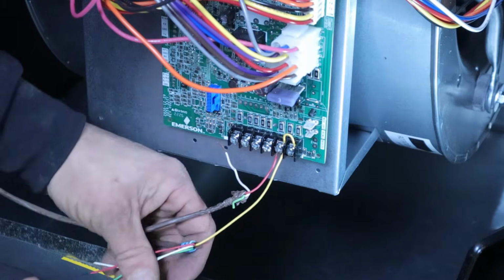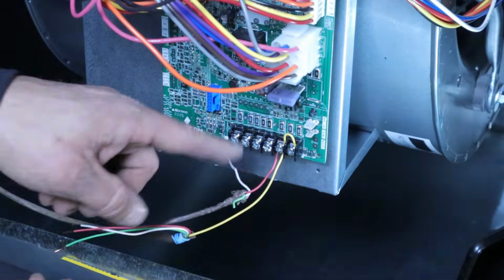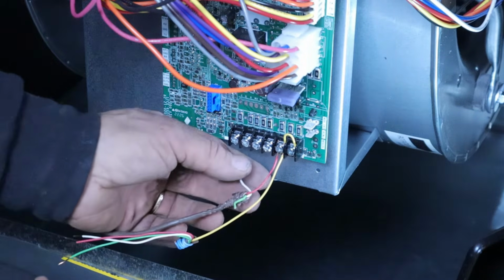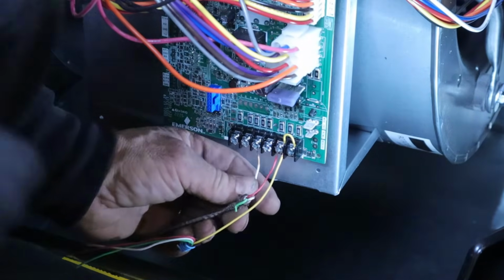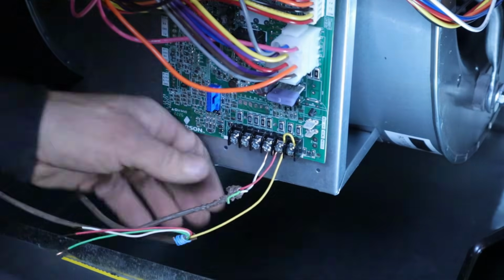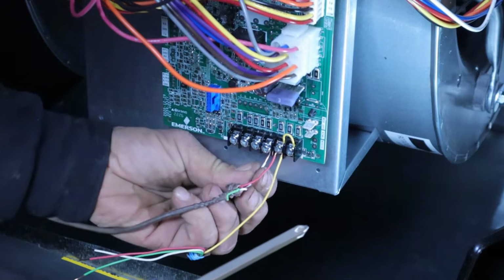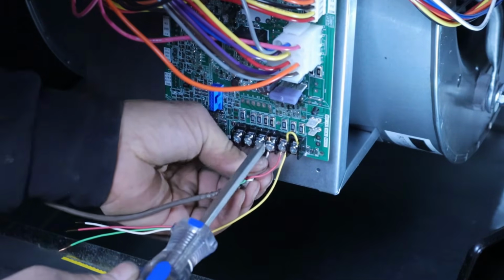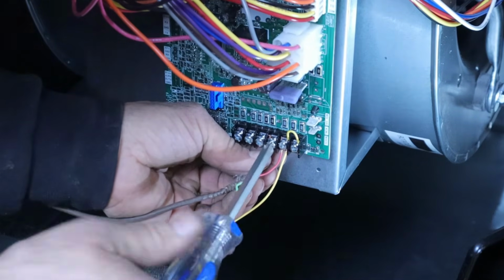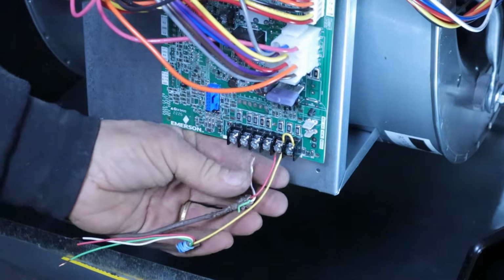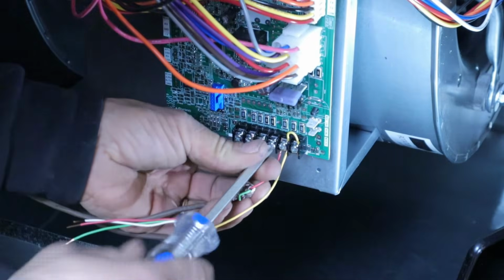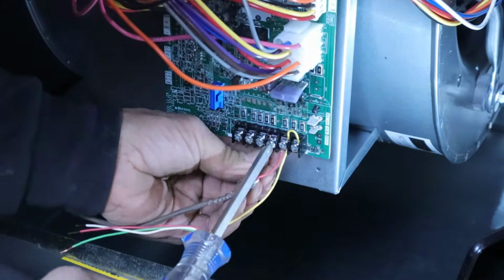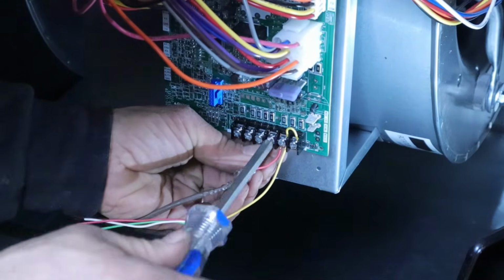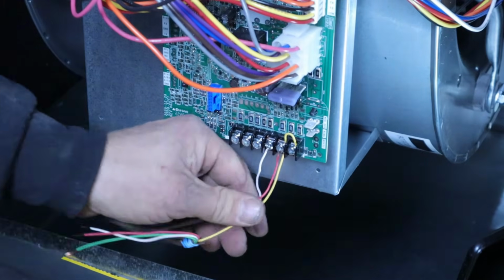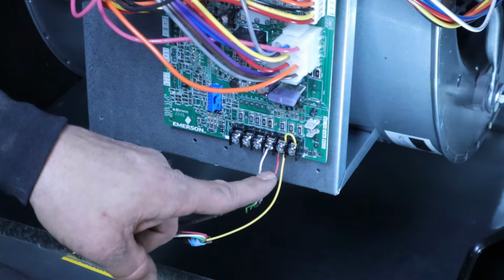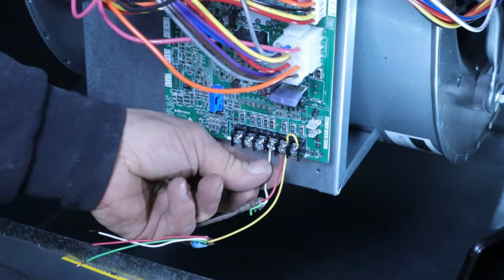So the white wire coming back from the condensing unit, that's our common. When the 24 volts goes out to the condensing unit to close the contactor, it's going to come back on this white wire, and we're going to hook that up to common. Our common connection is right here next to our Y. So we're going to hook the white from the condensing unit right up in there. Okay, so we have our cooling, our 24 volts for the contactor and the condensing unit on the red, and the white is the common coming back from the condensing unit.